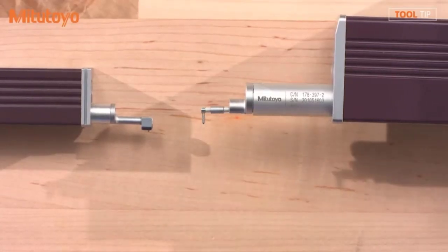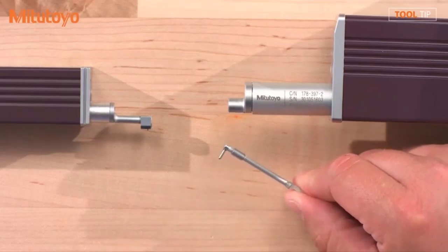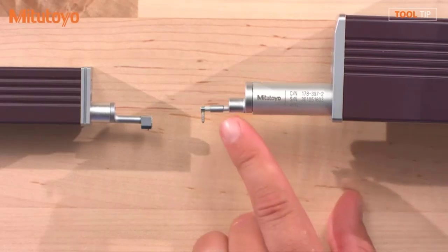Okay. So Drew, what equipment do we have here right now? I have two units, a skidded and a skidless system. These are both made by Mitutoyo, but they could be any brand of surface finish measuring system. All systems are made up of the same components. You have a stylus, which is the piece that contacts the surface to do the measurement. The stylus feeds into a detector. The detector takes the movement and translates it into a signal that can be measured, and then we have the drive unit, which pulls the stylus and detector assembly back and forth for the measurement. That plugs into an amplifier, which is where you get your readings from.